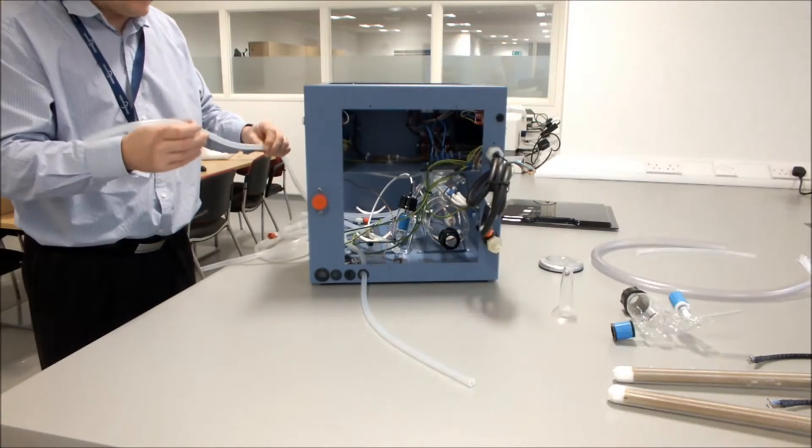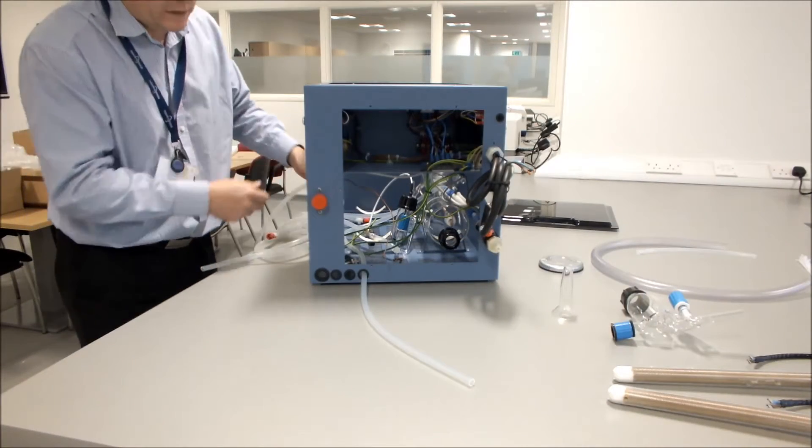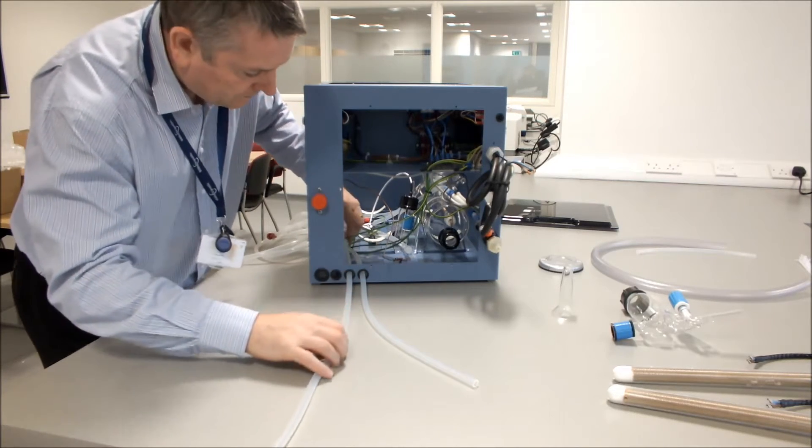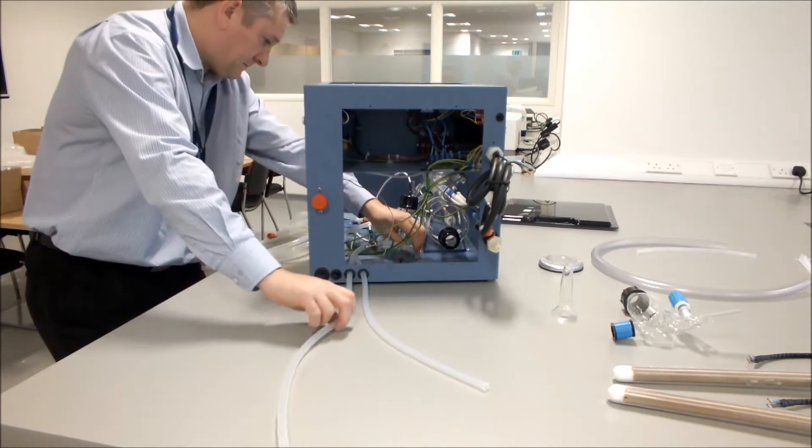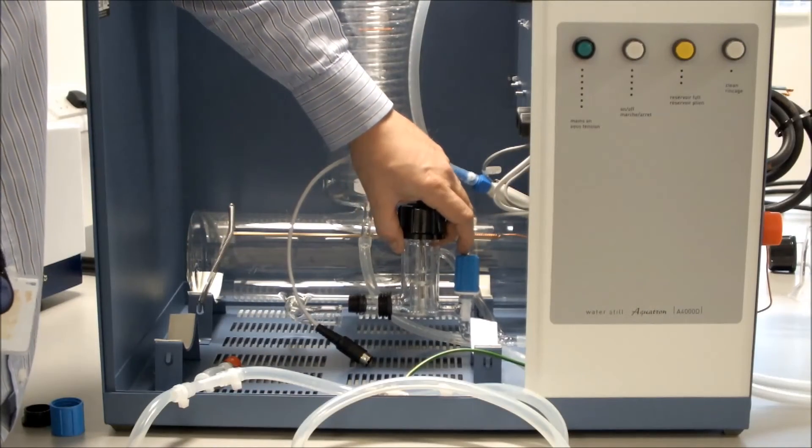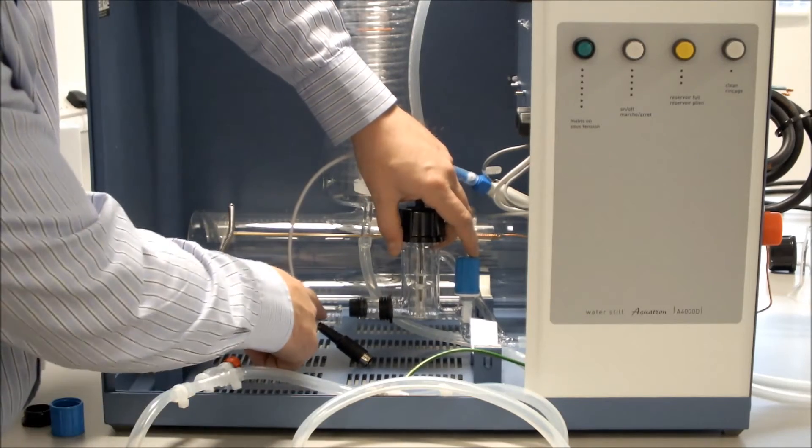We then thread through our 8mm tubing through the next available hole. Like so. What to do is to connect our rear boiler level control to our boiler itself.